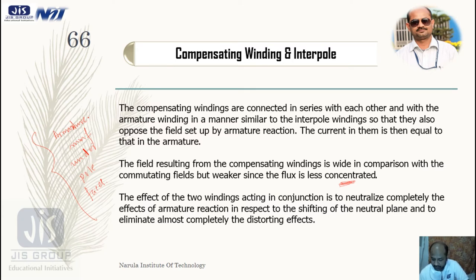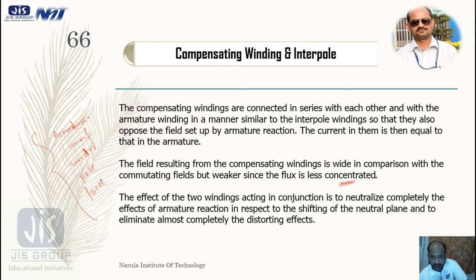One more thing to remember: provision of compensating winding requires additional space in the main pole faces, and it is made of copper, so it involves a larger cost. That is why in case of smaller machines we do not use compensating winding or interpoles. Rather, we use compensating winding only in case of larger machines.